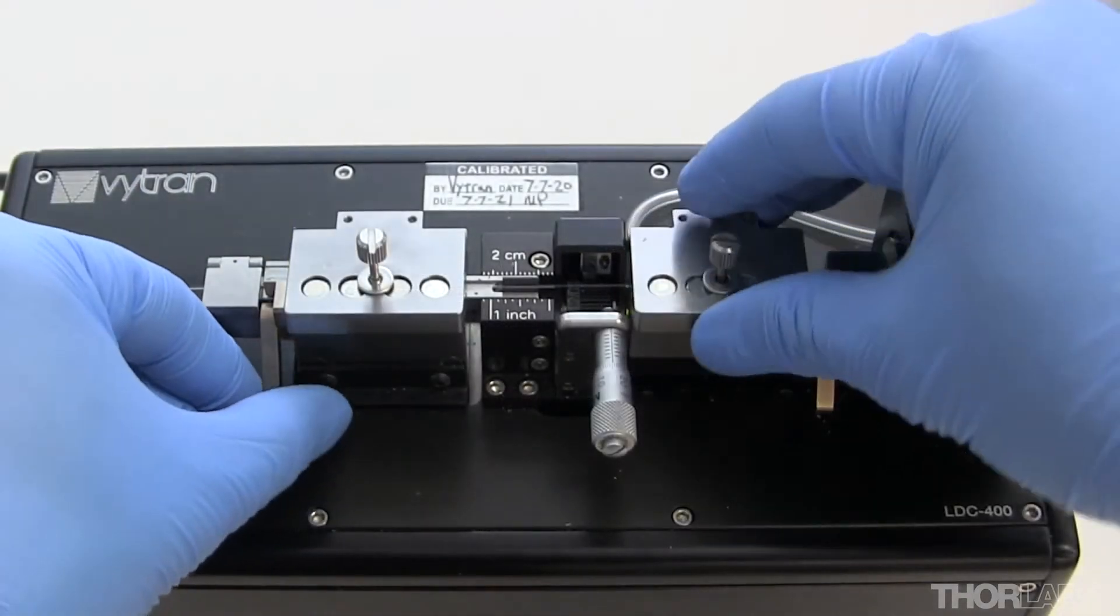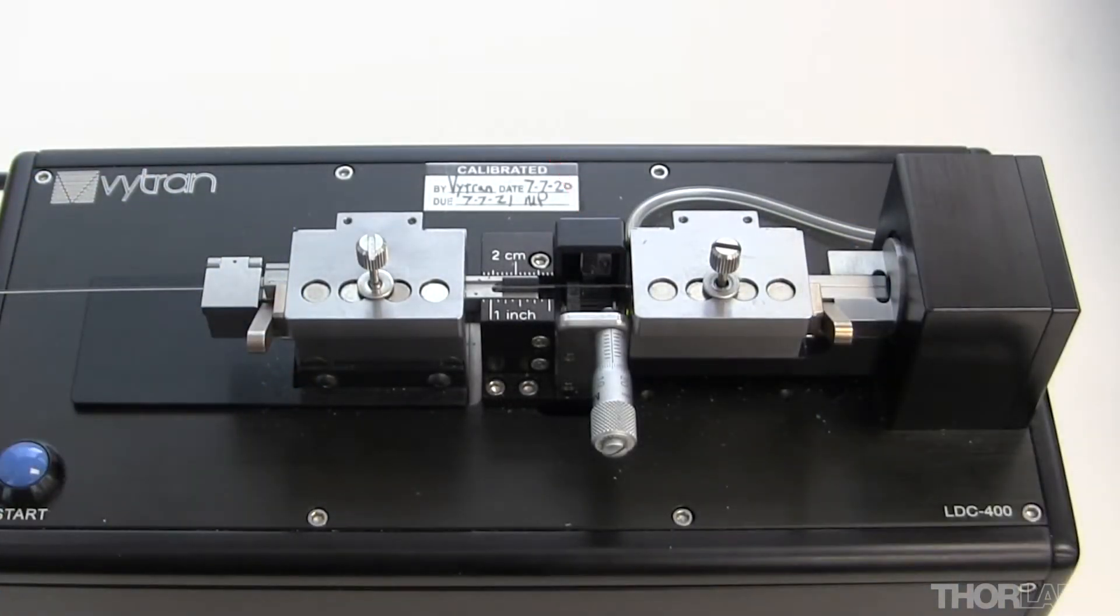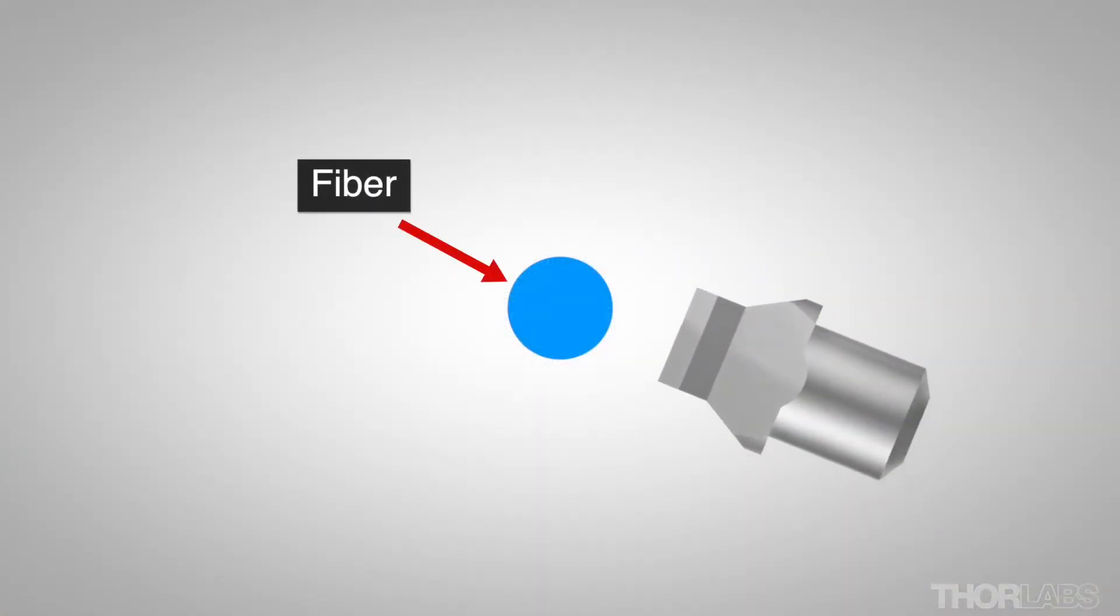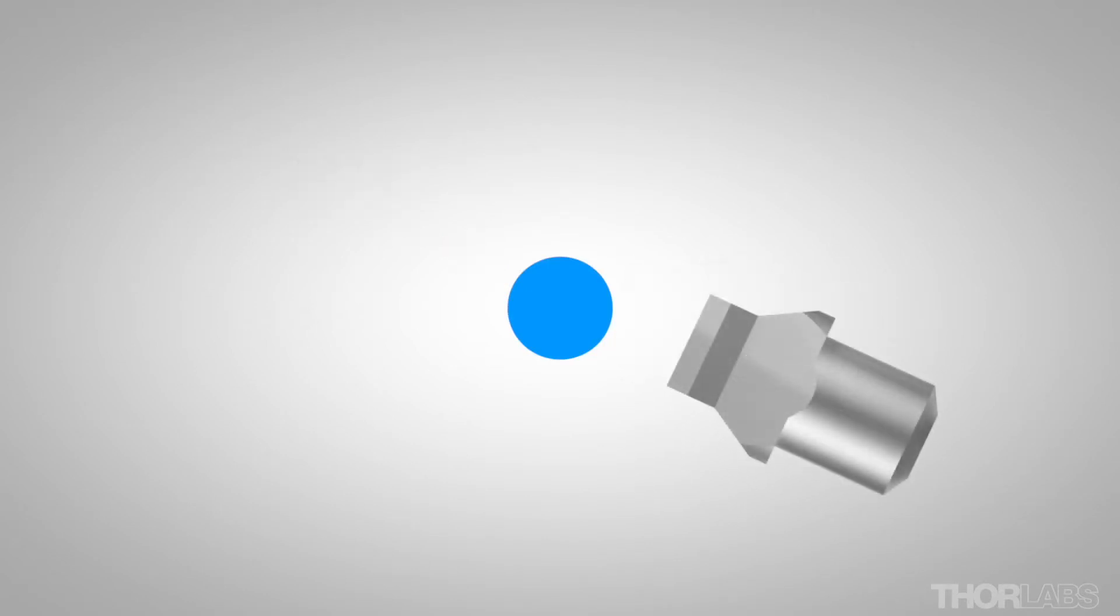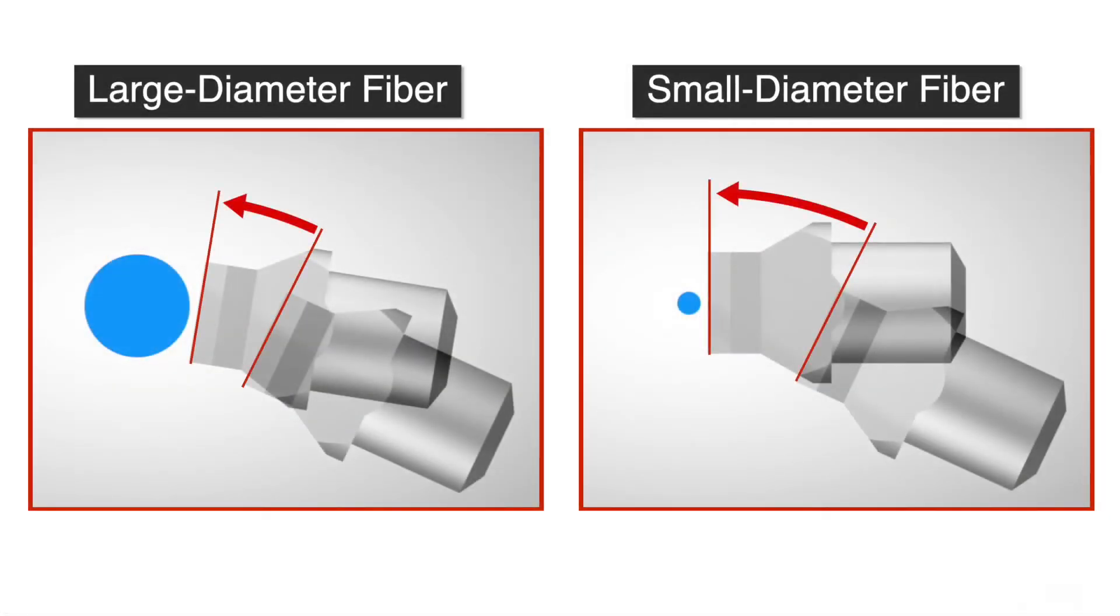When a cleave is performed, once the required fiber tension has been achieved, the blade will move forwards to its pre-cleave position, where it will be close to but not touching the fiber. The distance of this initial move is the blade offset distance plus the pre-cleave advance distance. This initial forward move will be smaller for large diameter fibers than for smaller diameters.